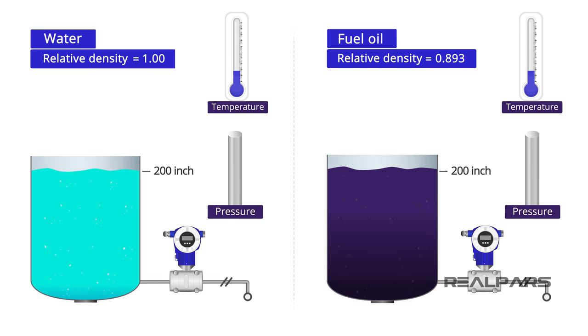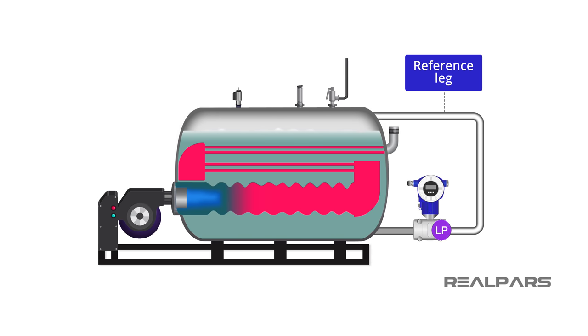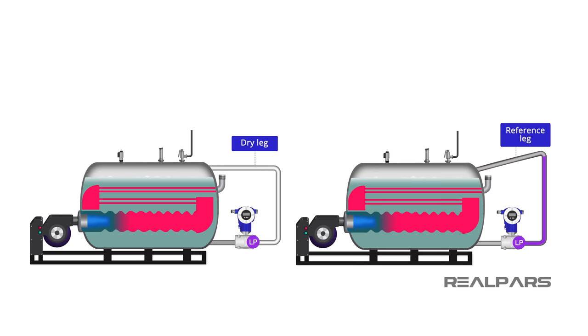Let's review what we have discussed. Liquid relative density and temperature have a significant effect on differential pressure transmitter level measurements. A reference leg is used to compensate for vapor pressure in closed vessels. A dry reference leg is called a dry leg. A wet leg is a reference leg filled with a liquid different from that in the vessel.